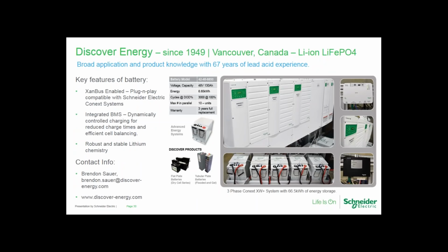Another battery type is the lithium iron phosphate solution, the Discover Energy solution out of Vancouver, Canada. Those are actually plug and play XanBus enabled batteries. So that's a really useful function. I've gotten a lot of feedback from customers that programming for the battery type and capacity really causes a lot of angst. They don't want to have to go through that step, and plug and play compatibility really adds a lot of value to not only the installer, but to the end customer. There's really no configuration that's required as far as battery programming goes.